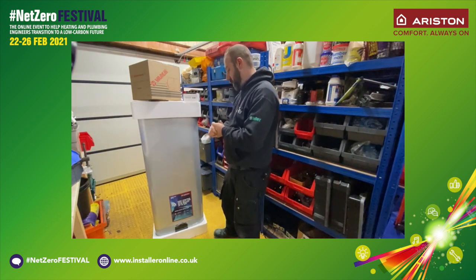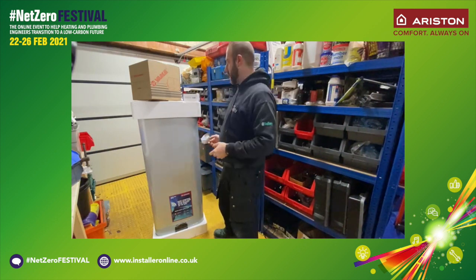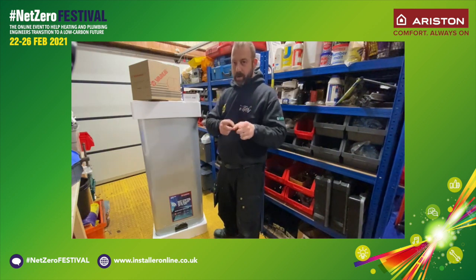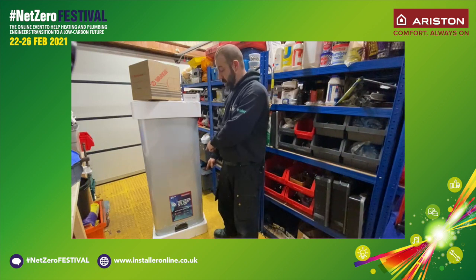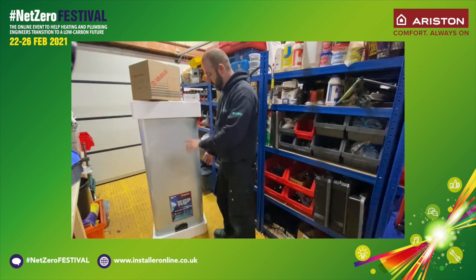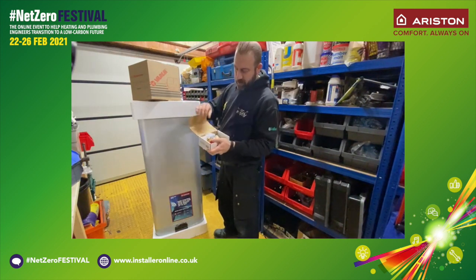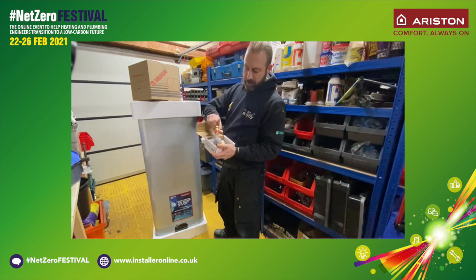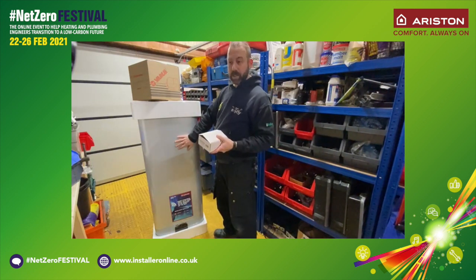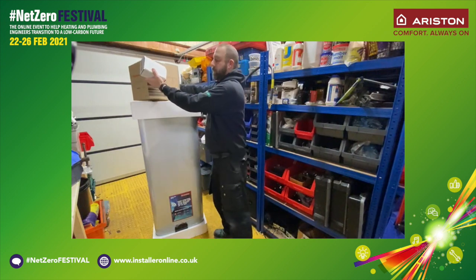Here we have the Ariston Velis Evo 80 Wi-Fi wall-hung water heater. I've taken the liberty of taking it out of its box and standing it upright for the time being. I will be flipping it upside down in a second because there are accessories hidden in the polystyrene underneath. So it comes in two boxes. The first box is the water heater itself with the hanging brackets etc. The second box is the pressure reducing valve and the tundish with pressure relief valve for the cold water inlet. And of course if you're fitting a water heater like this you should also expect to be fitting an expansion vessel as well, which is supplied as part of the kit.